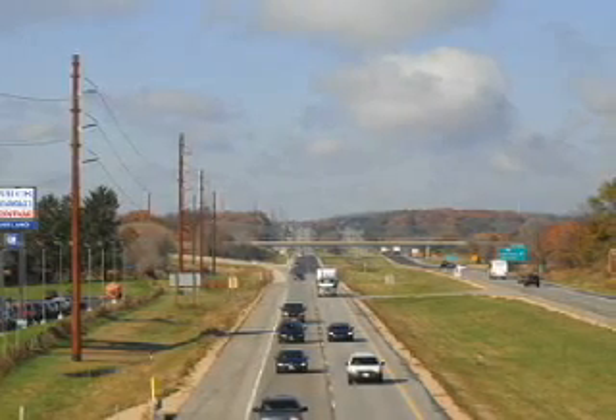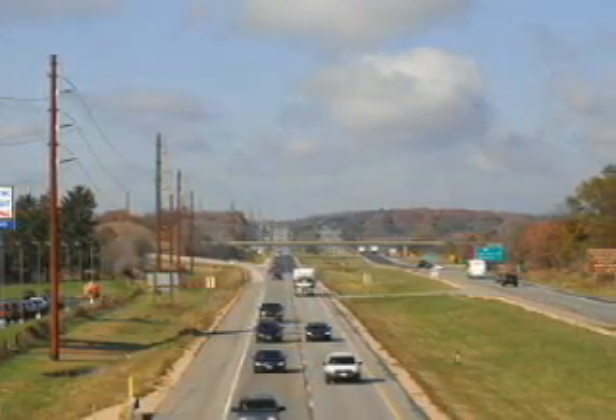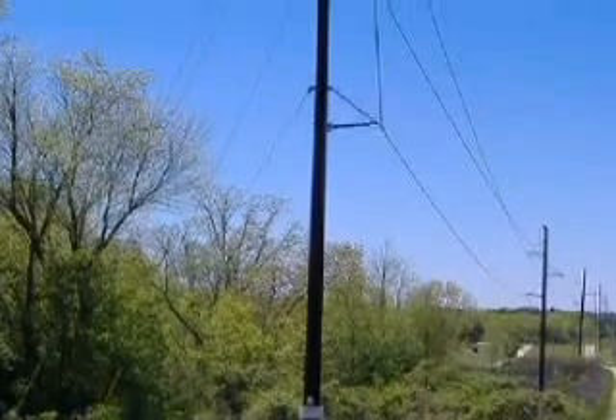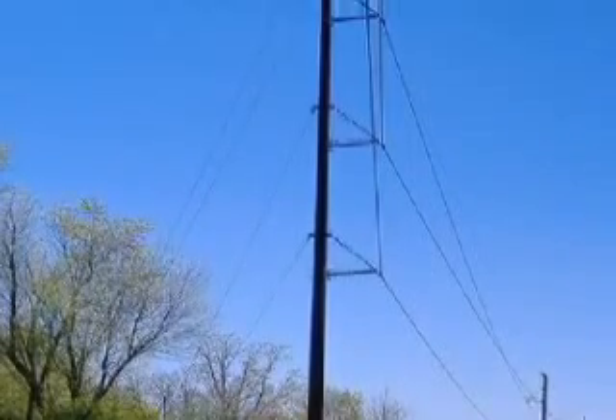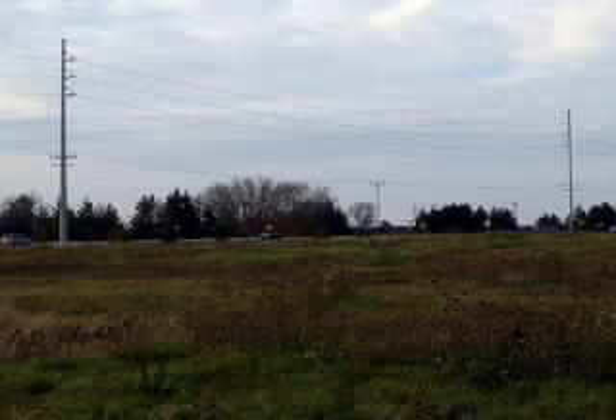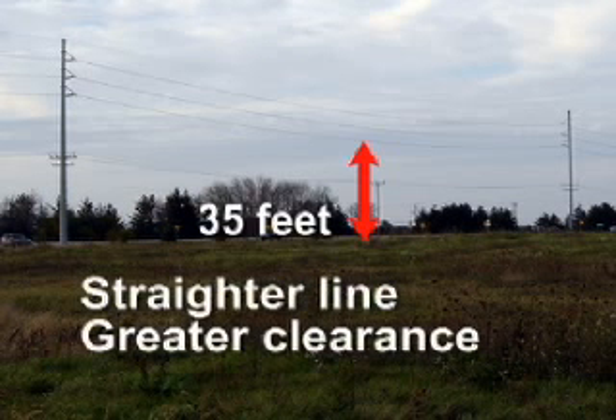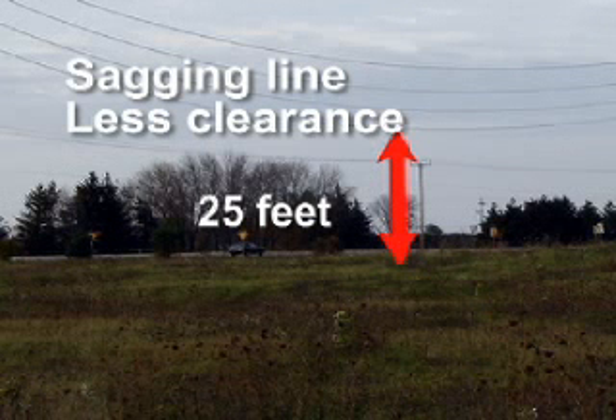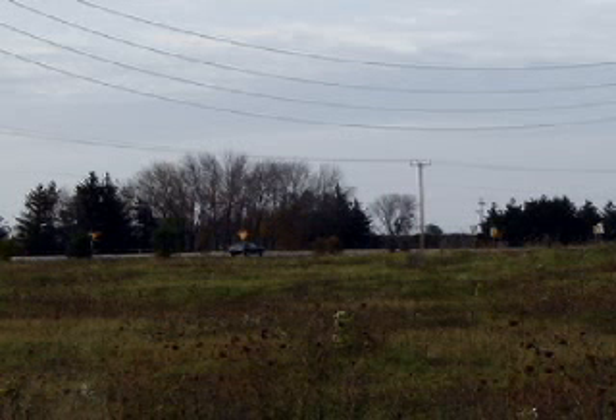Transmission lines have long spans and operate at high temperatures. During periods of high electric demand, the wires may sag a considerable amount. As a result, clearances may change from day to day as the line expands or contracts. For instance, on a cold day, a lightly loaded line may hang 35 feet above the ground. However, on a hot day, or if the line becomes heavily loaded, that same line may sag and have only 25 feet of clearance from the ground. You must always be aware of the amount of clearance between your equipment and an overhead line, and ensure that you comply with OSHA standards and account for possible line sagging as the temperature changes from day to day or during the workday.